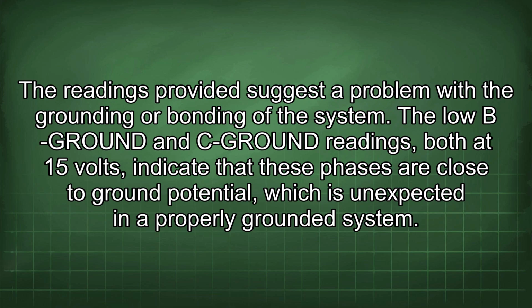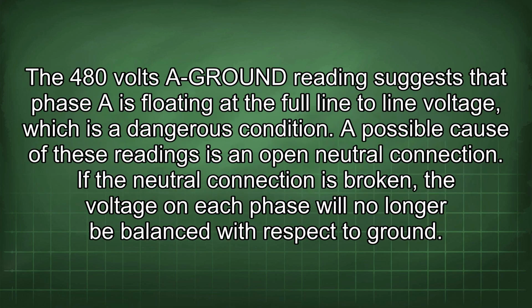The low B ground and C ground readings, both at 15 volts, indicate that these phases are close to ground potential, which is unexpected in a properly grounded system. The 480 volt A-ground reading suggests that phase A is floating at the full line-to-line voltage, which is a dangerous condition. A possible cause of these readings is an open neutral connection.